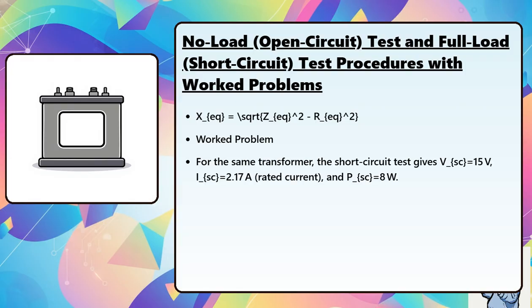Worked problem. For the same transformer, the short circuit test gives V sub SC equals 15 volts, I sub SC equals 2.17 amperes rated current, and P sub SC equals 8 watts. R sub EQ equals 8 divided by 2.17 squared, approximately 1.7 ohms. Z sub EQ equals 15 divided by 2.17, approximately 6.91 ohms.